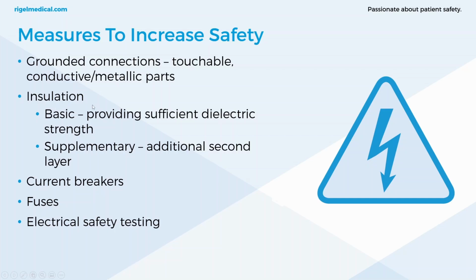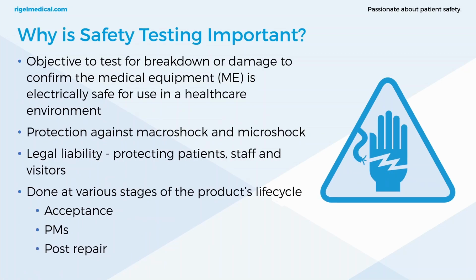We've also got insulation. There's basic, which provides sufficient dielectric strength, supplementary, which is an additional second layer, and it's class 2 devices that use this supplementary protection, so there's no earth connection required. The barrier is provided by that double layer of insulation.